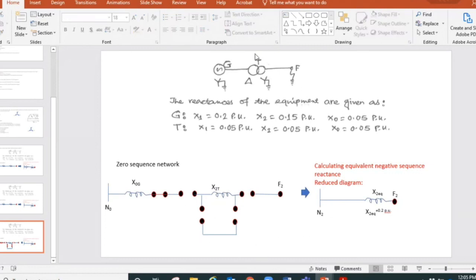So the drawing is done, but for the transformer, the connection type needs to be configured together with the grounding or not. This has to be connected. Now looking at this side, what is this side in terms of connection? It is delta. So when it is delta, if we remember, if the winding is connected in delta, we leave the shunt switch open. Sorry, if it is connected in delta, the shunt switch should be closed. The shunt switch should be closed.